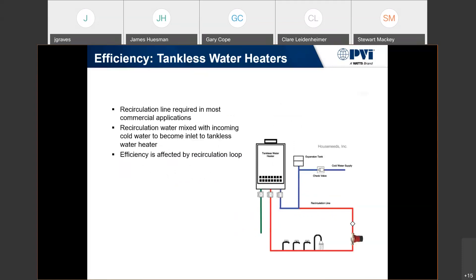In a commercial setting, we're going to have recirculation systems. In a true instantaneous commercial system, you have incoming cold water, a hot water outlet, recirculation going out into the system loop, and then we bring it back and tie it into the cold water feed to the appliance. What we're doing is preheating the cold water feed — changing the equation of the original test procedure of 70 degrees on the incoming. We need to take that into consideration when talking about efficiency.